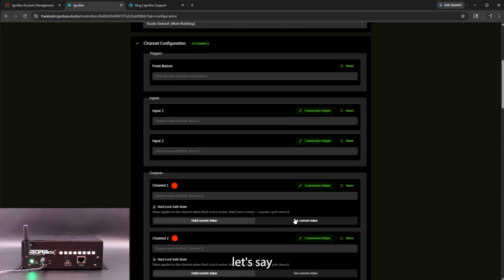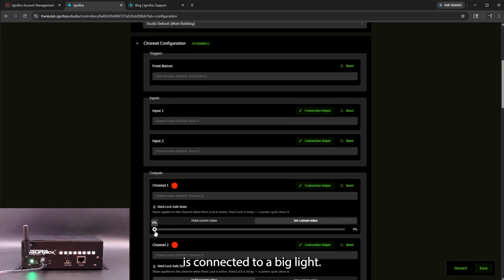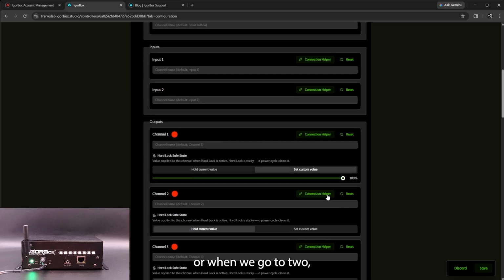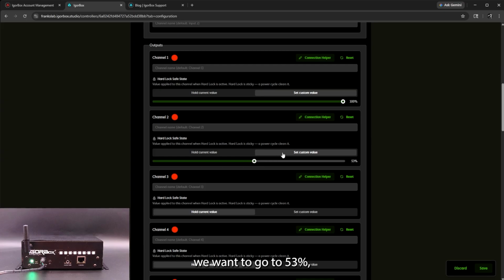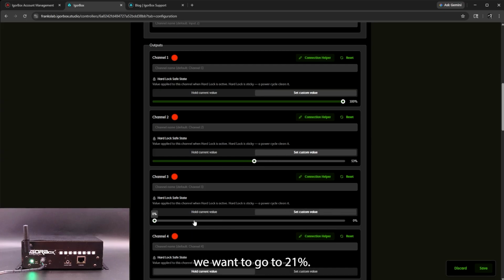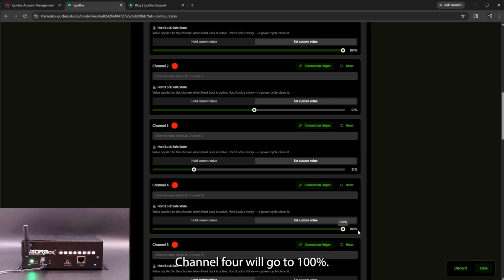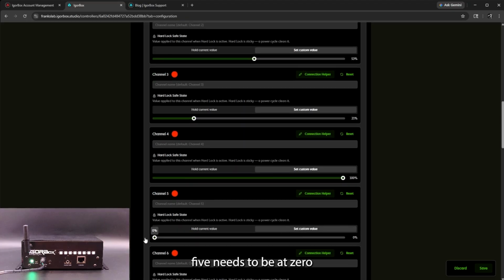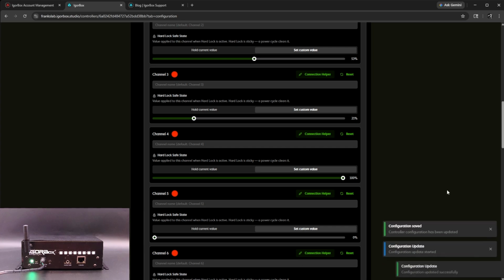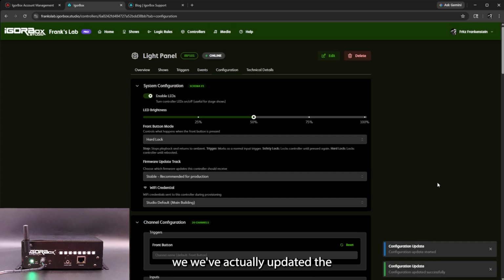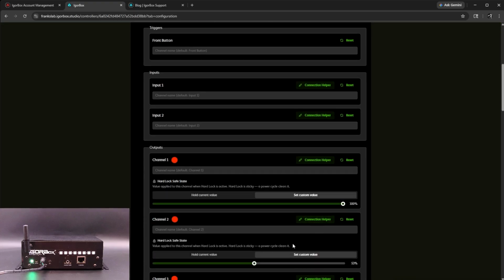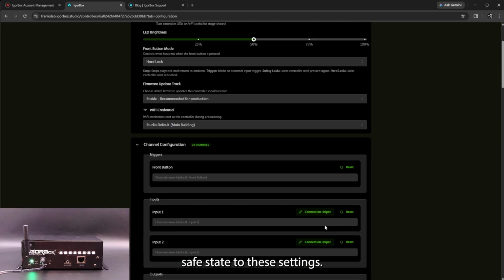But let's say channel 1 here is connected to a big light, and we want that light to go to 100% when we go to safe, or when we go to this hard lock state. Maybe channel 2 we want to go to 53%. Maybe channel 3 we want to go to 21%. Channel 4 will go to 100%. Maybe channel 5 needs to be at 0, no matter what, right? So now if I hit save, you can see that we've actually updated the hard lock safe state to these settings.